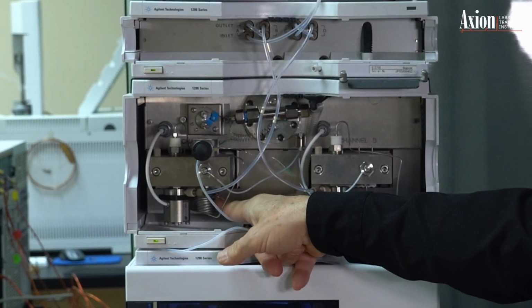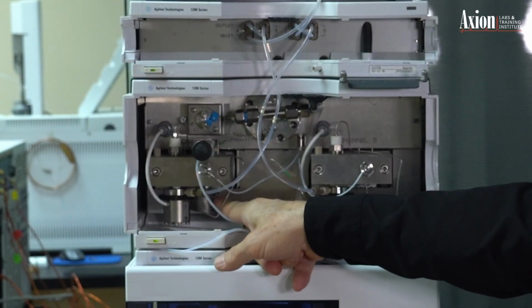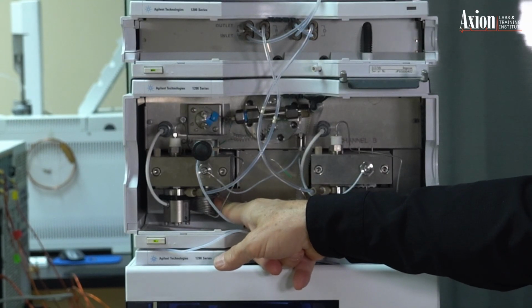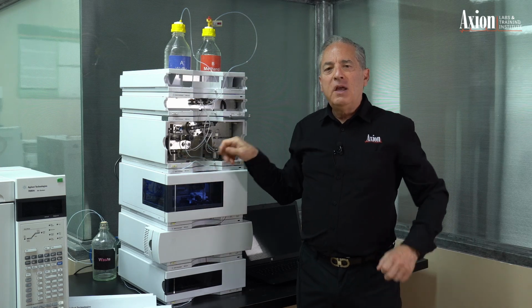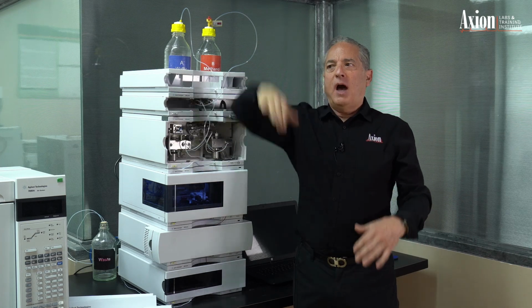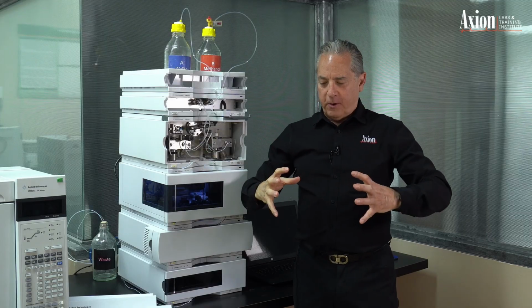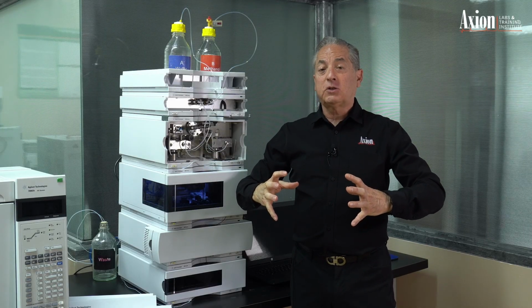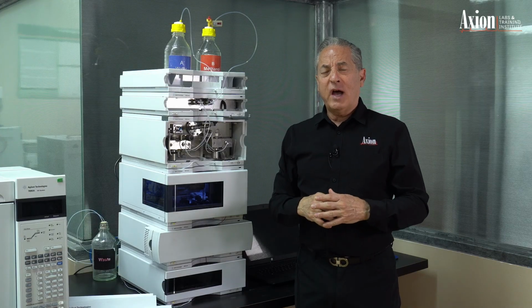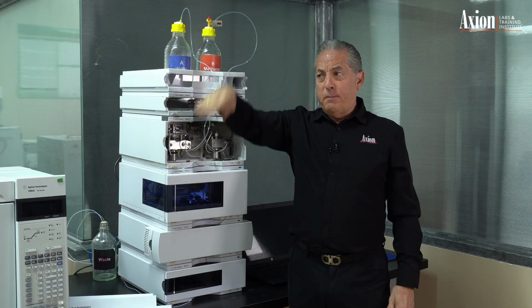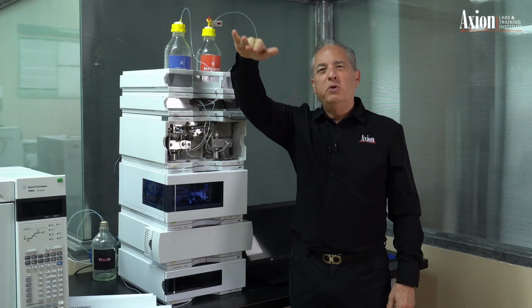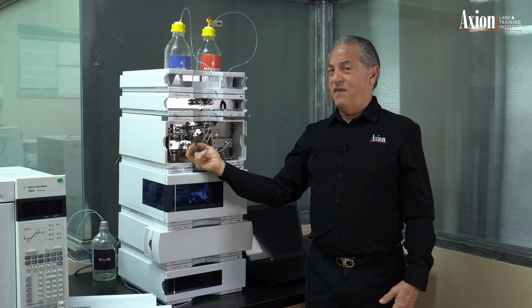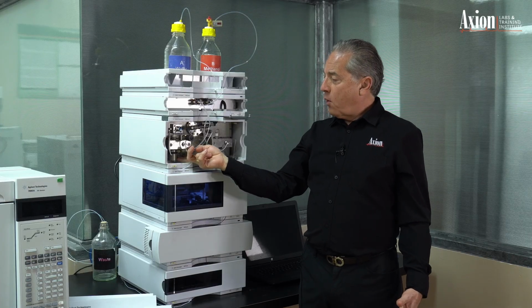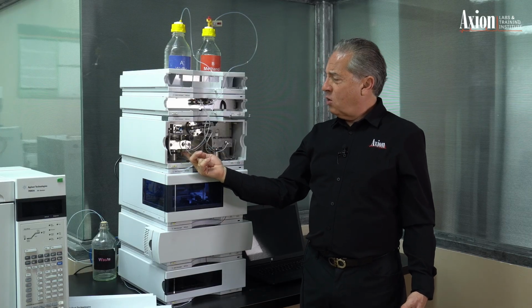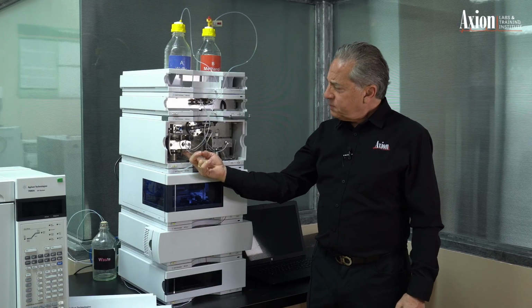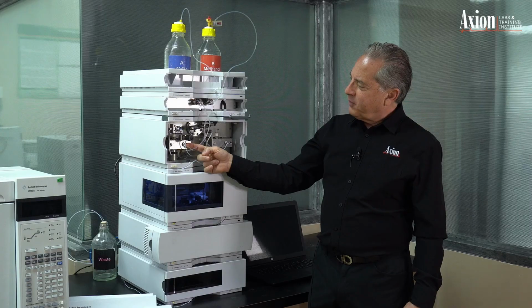Now, if you notice this coil of tubing, this is great to see because this is very old school, which means it's tried and true and it works great. And this is a pulse dampener. So with the pulse dampener, you think about this piston going forward and back, so high pressure, low pressure, high pressure, low pressure. Well, this pulse dampener will expand and contract just to absorb those shocks. Like the shock absorber on your car, when you have a very bumpy road, it doesn't get rid of the bumps, but it smooths them out. So this removes the vast majority of the pulsation from piston A before we go into piston B. So piston B is pumping, and then coming out of piston B, it comes out the front of the pump.